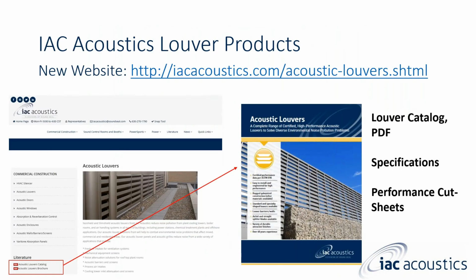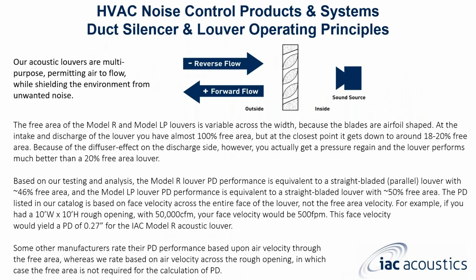Moving on to our Louver products, you can see right here at our website where you can download our Louver catalog, specifications, and performance cut sheets here as well. The nice thing about Louver operating principles is forward and or reverse flow in correlation with the sound source. Our louvers are multi-purpose, permitting airflow in forward and reverse while shielding the environment from unwanted noise. Now, what you see up there is a representation of our Model LP louvers. Model R is a regular louver, LP is lower pressure drop.